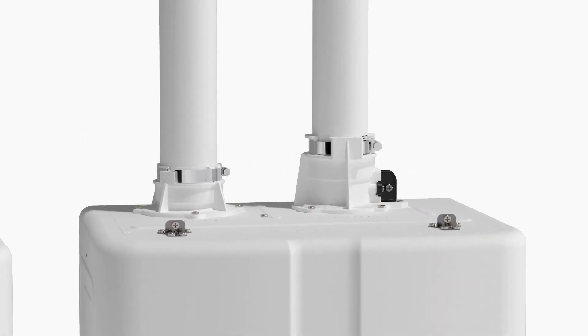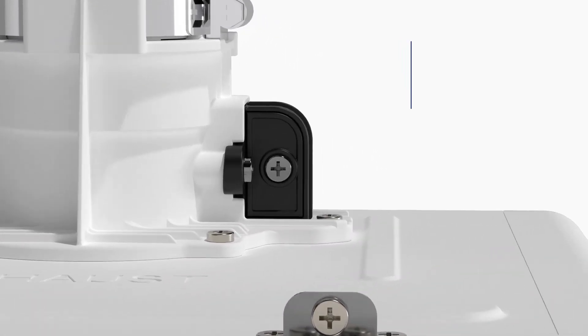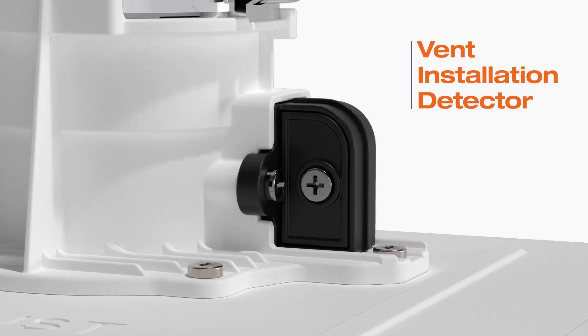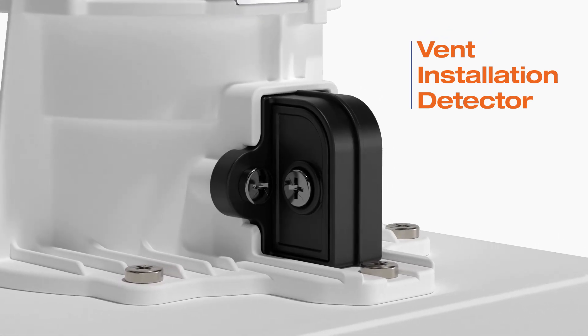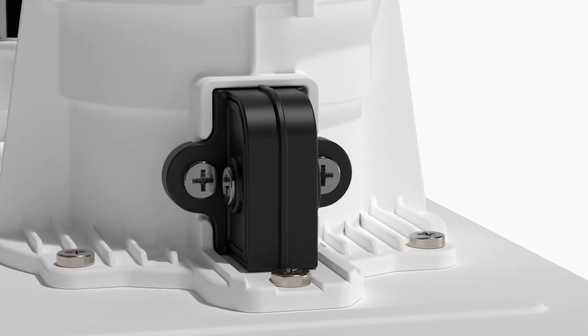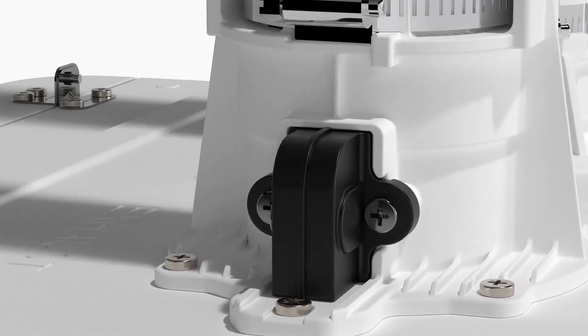What does VID do? Connected to the vent collar, the VID detects whether the vent pipe has been inserted into the collar at a sufficient depth and signals improper installation at the time of setup.